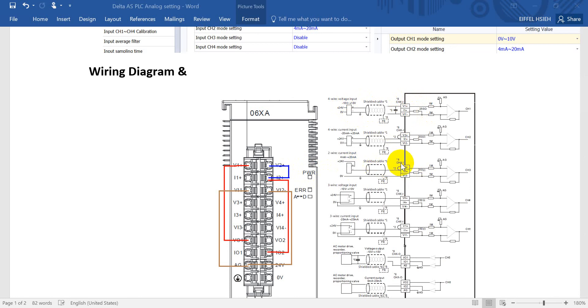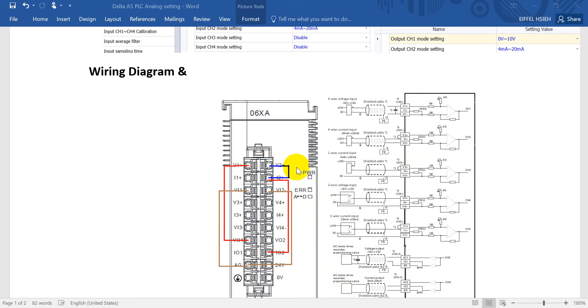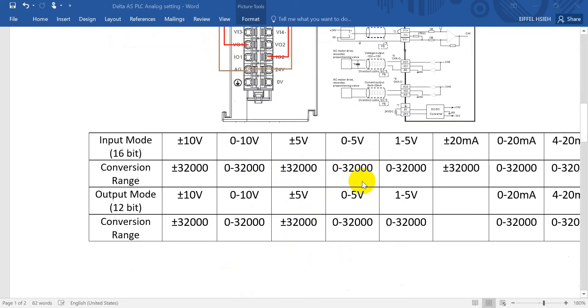Regarding current input, we have to short circuit V plus and I plus. Here we use channel 2, which means we have to short circuit V2 and I2 plus. On the other side for 0 we connect to AG. That's the wiring for voltage and current input.